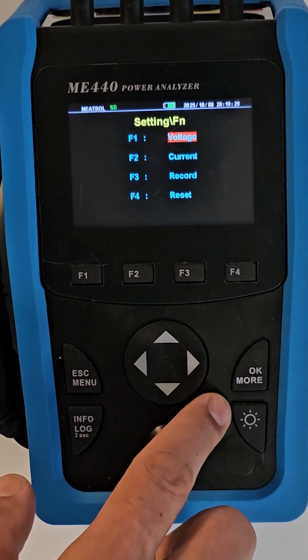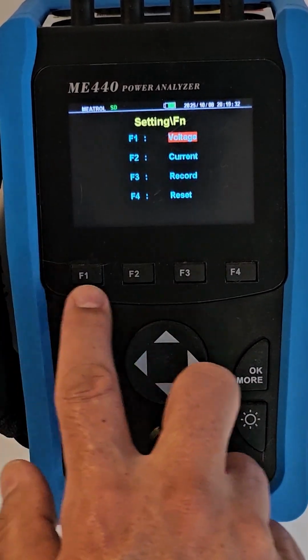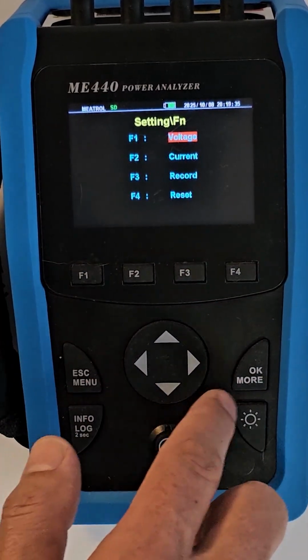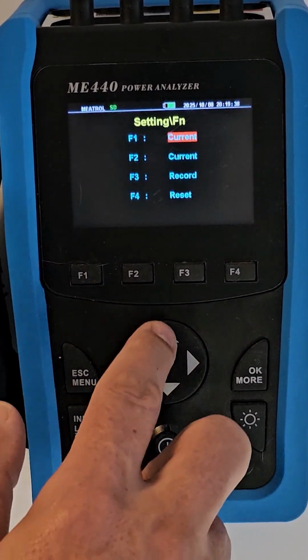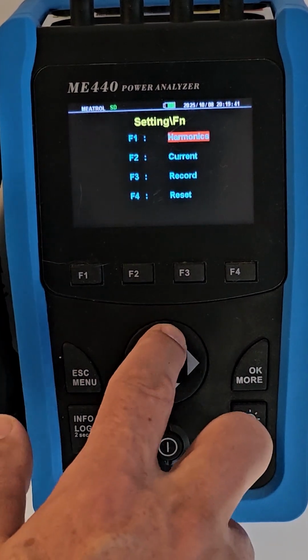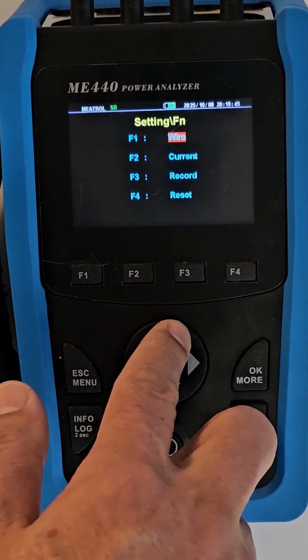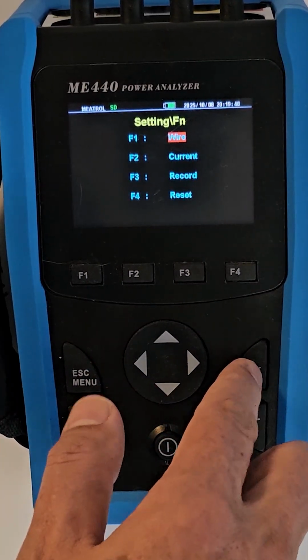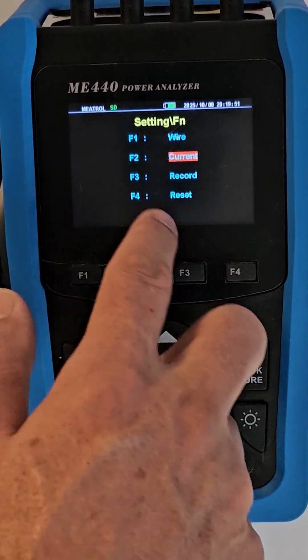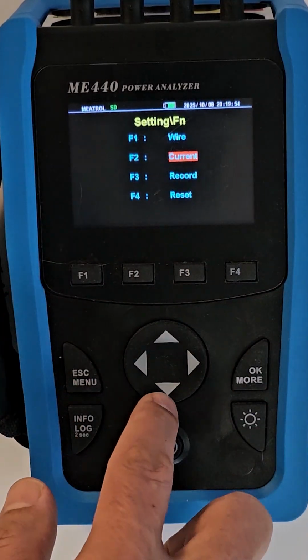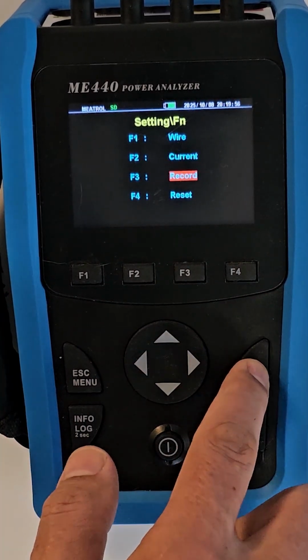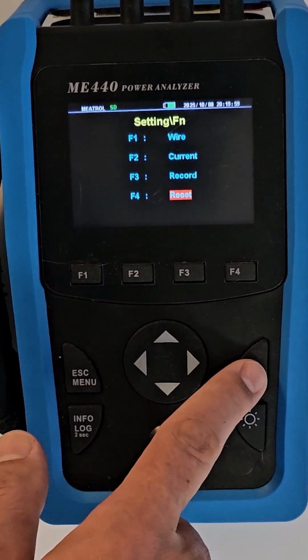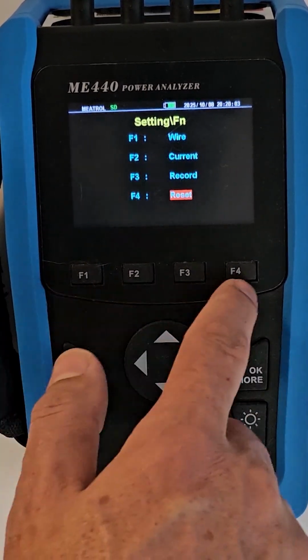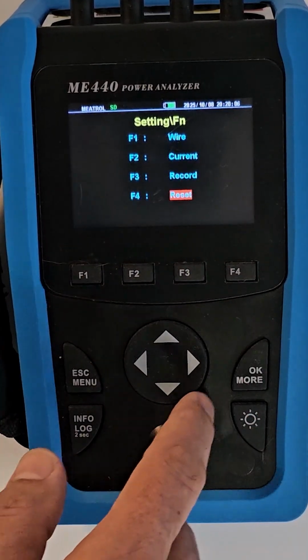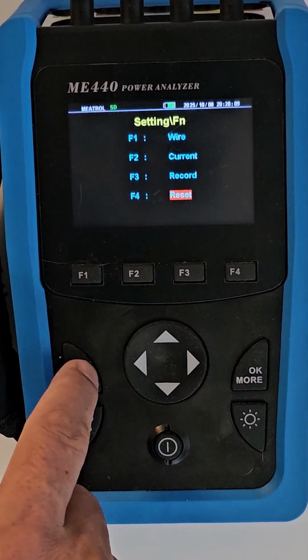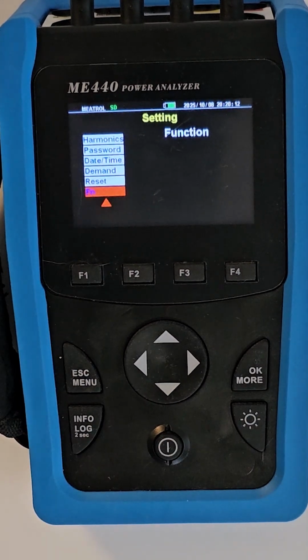Okay, and lastly you can go to the function menu, and here for these different function buttons you can assign different functions. So for example F1, you can go to the voltage, the current, the wire. So typically wire is a good option there. Here you can set either CTs or Rogowski coils. There you can do the enabling and disabling of recording and download data, and there you can reset the maximum values and peak values and energy. So that's these shortcut buttons that can access those menu items. Okay, and then just save the changes.